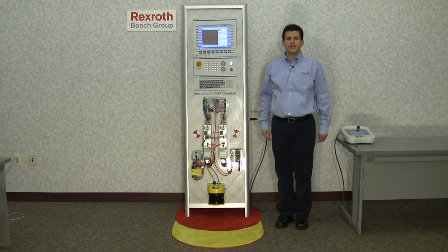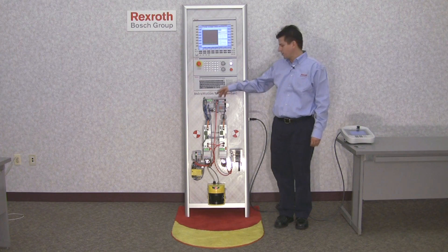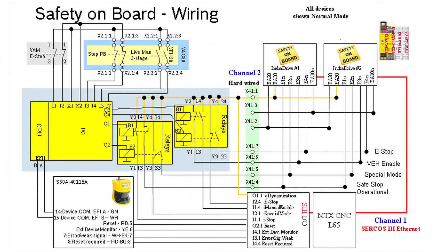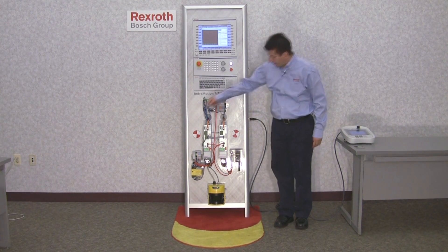Here we have a CNC machine control demo. It has a CNC control MTX IndraControl L65 with SERCOS Ethernet communication interface, two IndraDrives with safety on board technology, and a laser scanner connected to a configurable safety relay that are directly connected to the IndraDrives and the MTX control. Channel 1 is done through the MTX control using the SERCOS Ethernet. This way the control knows what safe mode is selected and automatically reduces the motion settings by selecting appropriate speed, direction, stop modes, or anything to avoid nuisance errors by triggering the safety specifications in the drive. The selected safe monitoring is made in the drive. Channel 2 is wired directly to the drives.